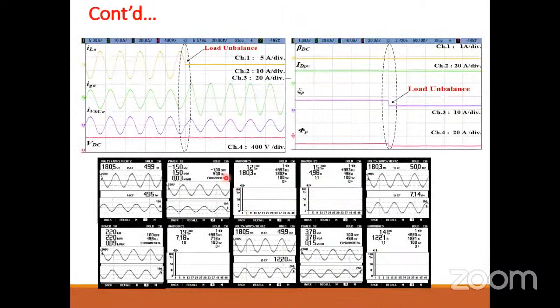Similarly, on the experimental setup you can see the same thing: the linear load conditions, the first one is the load current, and then the load unbalanced condition. Because of this unbalance, you can see the load current component decreases and the grid current component increases. Again, this is the axis line, so above it is the positive component and below it are the negative components. So in the negative domain this is increasing, in the positive domain this is decreasing. During the unbalance, the DC voltage is almost okay, right? And if you go to the harmonic analysis, you can see the THD here. The grid current THD is around 1.5%, and the load current is 1.19%. Both are linear, so no issue with that, and everything is working very fine.